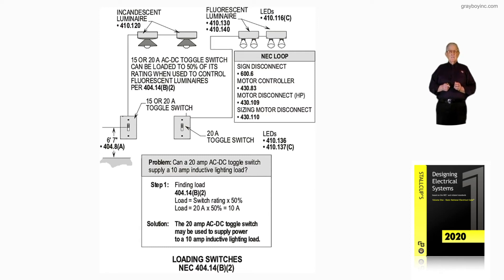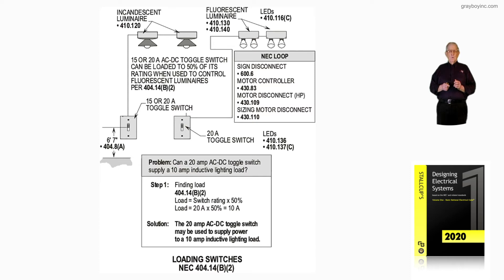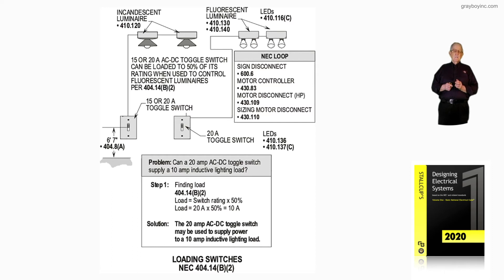The question in your problem is: can a 20-amp AC-DC toggle switch supply a 10-amp inductive lighting load? To apply the 50% rule in accordance with 404.14 B as in Boy 2, Step 1: take 50% of 20 amps, which equals 10 amps. The answer is yes — we can take 50% of that switch and feed inductive loading.